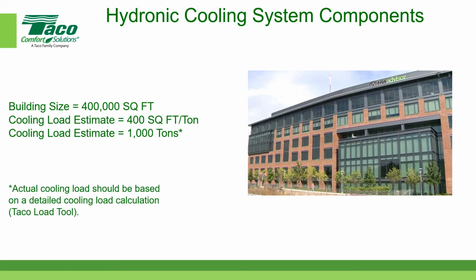What it means is that the actual cooling load should be based on a detailed cooling load calculation. So whenever we're trying to get an order of magnitude something, we could use 400 square foot per ton. It gives us a ballpark number of how big the equipment should be, and then we can use that for conceptualizing things like that. But when it gets into the actual selection of equipment, you should do a detailed cooling load calculation. And we actually offer the TACO load tool, and I'm going to put the link here.